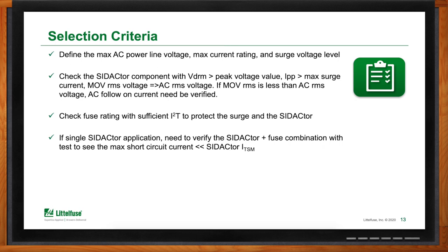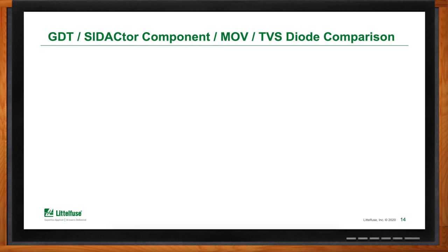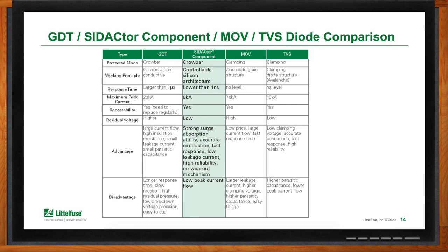How does the SIDACtor compare with other protection technologies? The technologies currently most used are GDT and SIDACtor, which are crowbar devices, and MOVs and TVSs, which are clamping devices. The SIDACtor is a solid-state crowbar device with much more refined capability than a GDT — much faster turn-on and very high power handling capability. Combining SIDACtor technology with an MOV can yield a much lower and in many cases superior clamping voltage to protect the circuit.